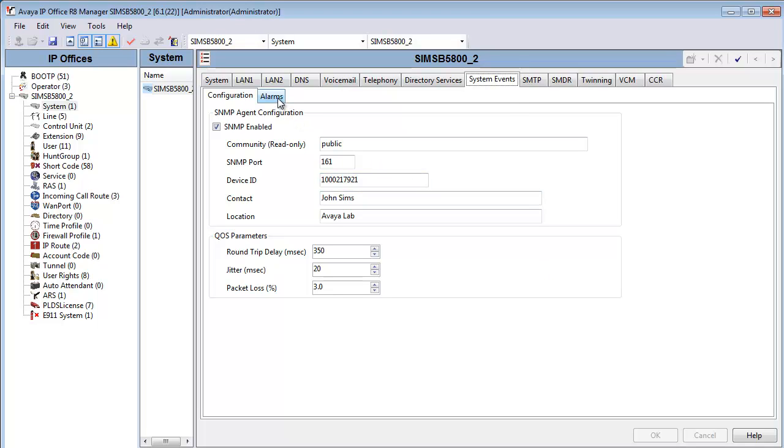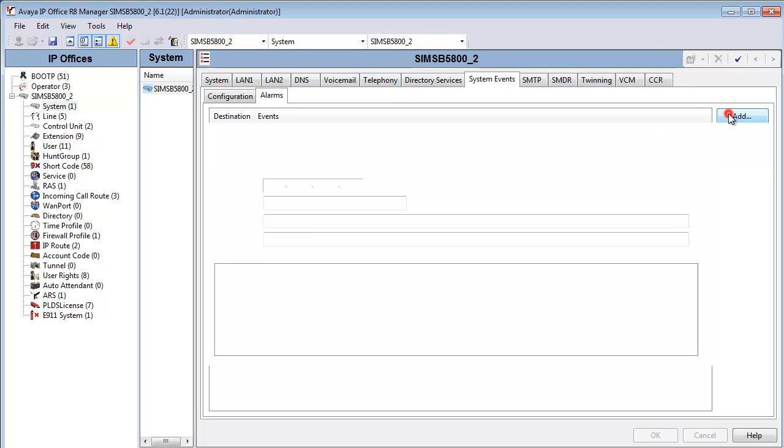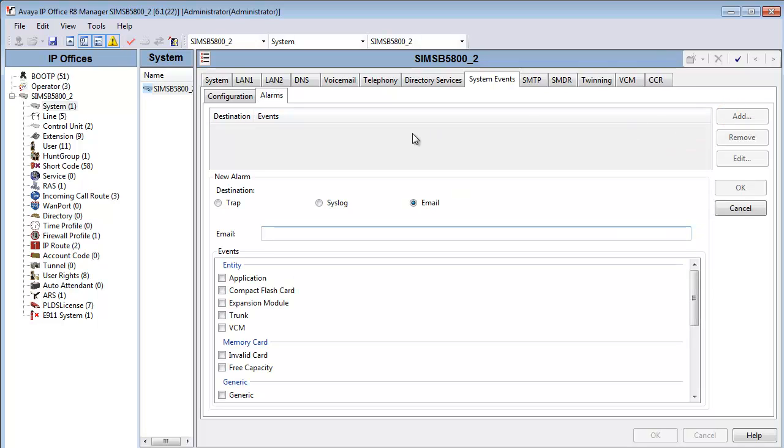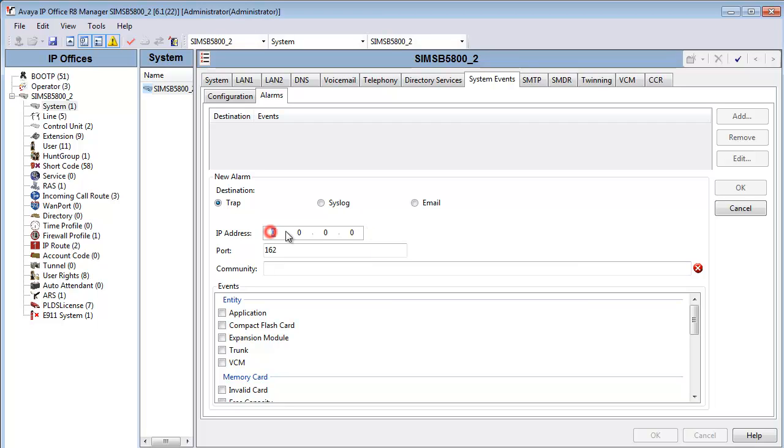Now that we're finalized on this configuration form, let's head into the alarm tab. Under the alarm tab, we'll click add and it's here that we can select our alarm destination option. We have three to choose from: email, syslog or trap. We'll select trap. We'll be sending SNMP traps to SAL. Here we'll add the IP address of the SAL gateway, which will act as our alarm receiving host, and we'll leave the port on UDP 162.